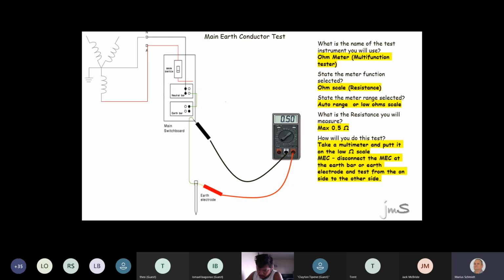Your wire might be broken, but in the meantime, you get a good reading because your soil is wet and your transformer is close by. You're going to get a false reading. So it's possible that this reading you're going to get, that wire is broken, but you get a parallel path back. I'm just warning you what could happen.